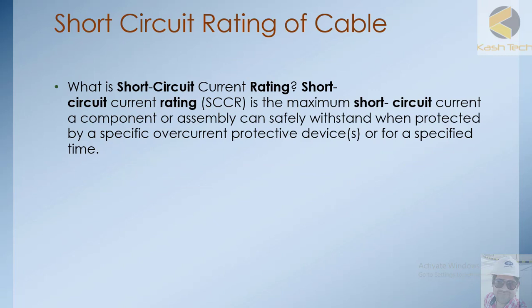What is the short circuit rating? The short circuit current rating is the maximum short circuit current a component or assembly can safely withstand when protected by a specific device for a specific time. A short circuit rating applies when there is a source and the load is bypassed — the source is short circuited. All manufacturers provide a short circuit rating given with a specific time duration.